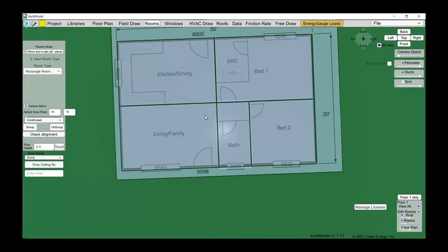You want to make sure that your entire floor plan is covered with a box so that every part of the house is included in at least one room or the other. If for some reason you weren't paying attention and you made this little box a little shorter than it should be, if you look right here, there's this little tiny sliver of house that's not included in the boxes we've drawn. If we were to leave it like this, the software thinks that's a little courtyard, a little 1 foot by 5 foot wide courtyard. And so it's going to treat this as an exterior wall. Imagine a little hole protruding down inside the house. And now all these walls that are adjacent to that little box are now exterior walls. Well, we don't want that.